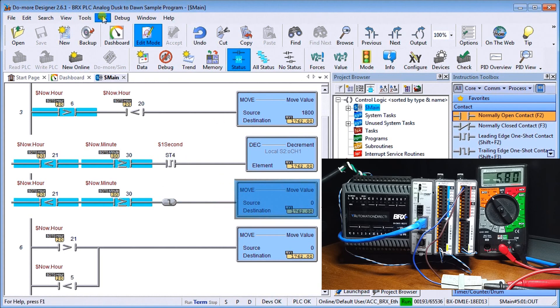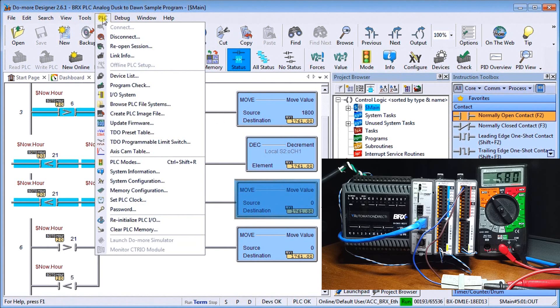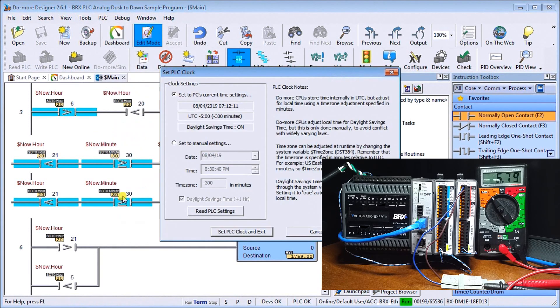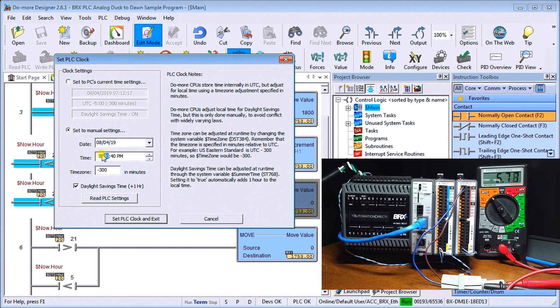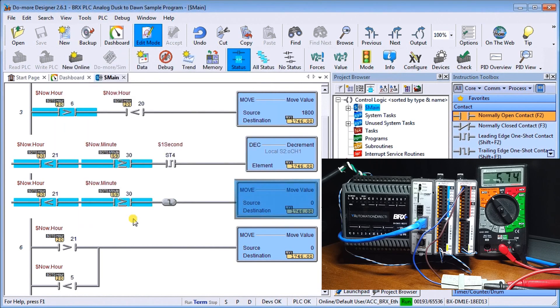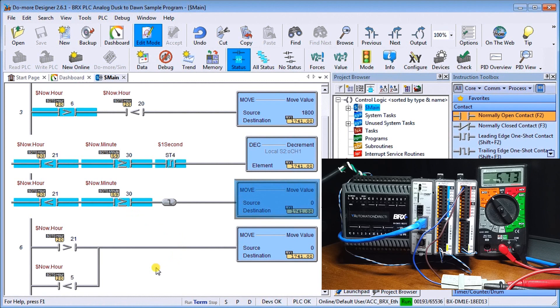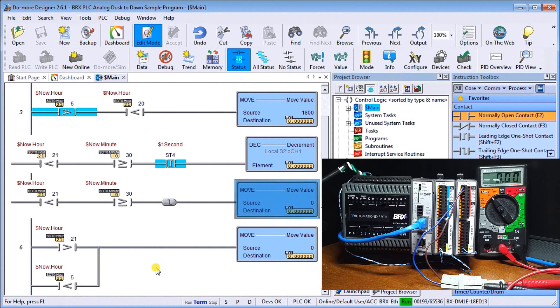So let's go again, PLC, we'll set our time and we will set it to 8:59:55. So once we set it, as soon as I go to nine o'clock, it automatically puts zero in, which then zeros out our analog. So our lights are now off again, and they will remain off.